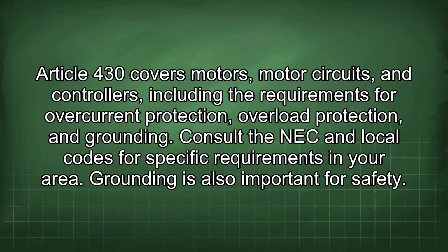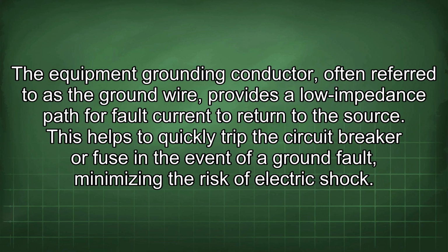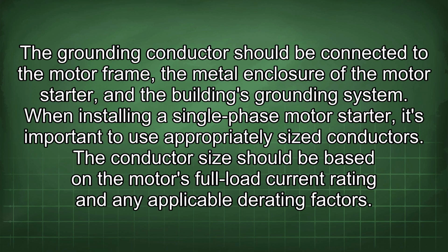Grounding is also important for safety. The equipment grounding conductor, often referred to as the ground wire, provides a low impedance path for fault current to return to the source. This helps to quickly trip the circuit breaker or fuse in the event of a ground fault, minimizing the risk of electric shock.